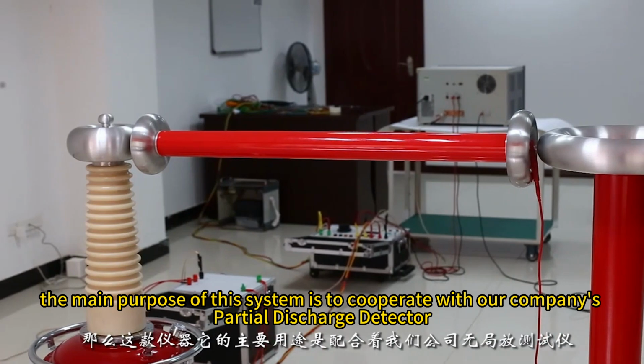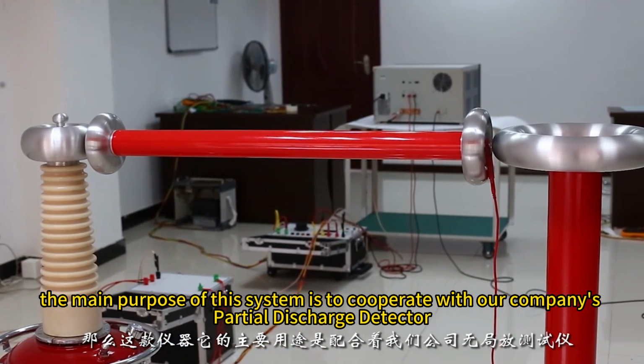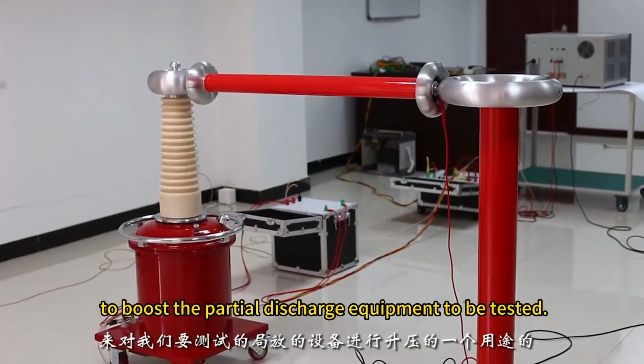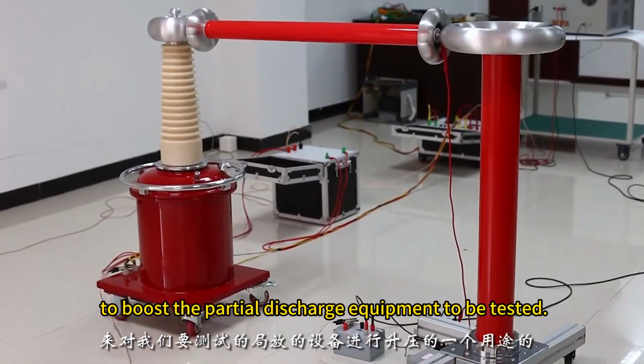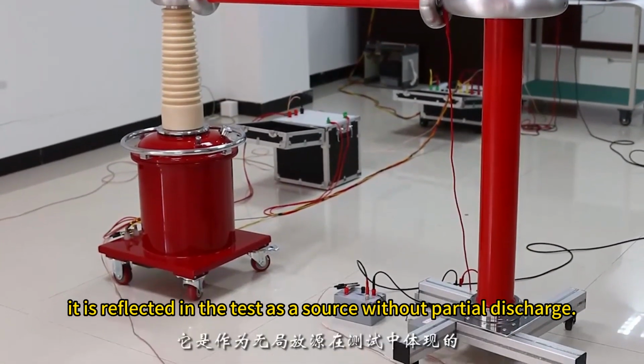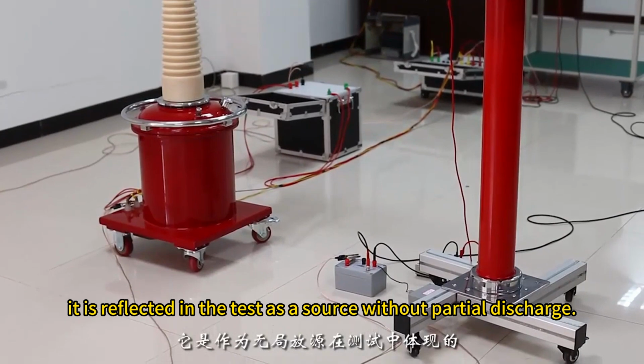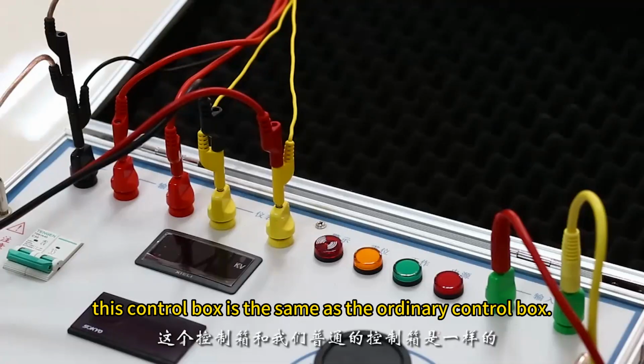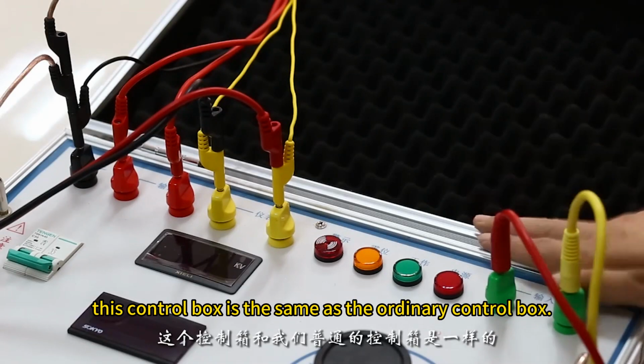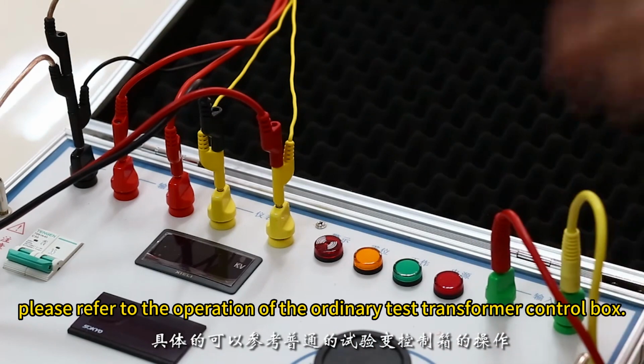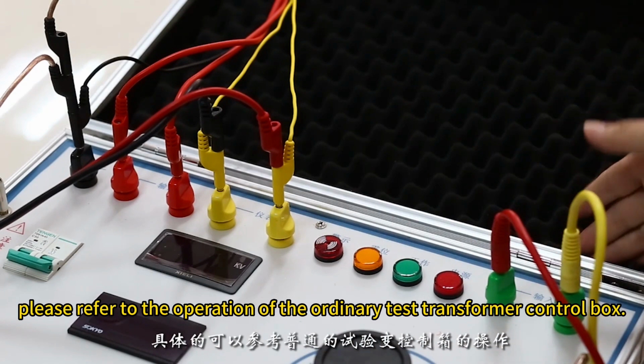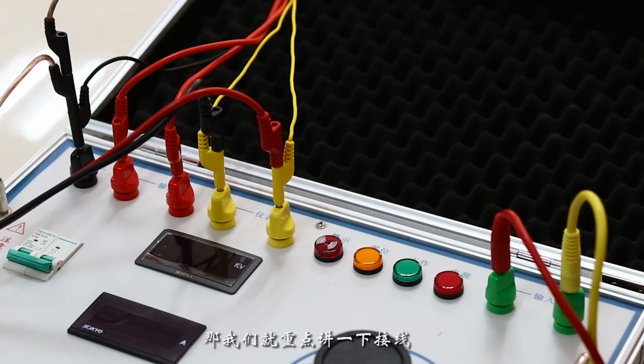The main purpose of this system is to cooperate with our company's partial discharge detector to boost the partial discharge equipment to be tested. It is reflected in the test as a source without partial discharge. This control box is the same as the ordinary control box. For specific use, please refer to the operation of the ordinary test transformer control box. Then let's focus on the wiring.